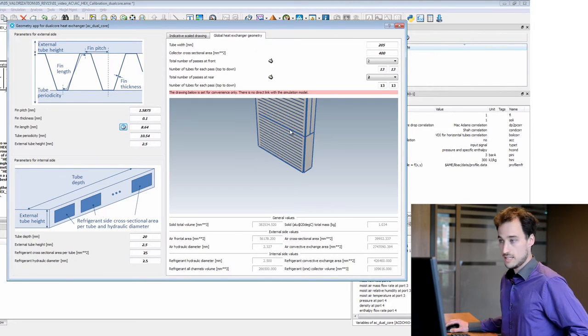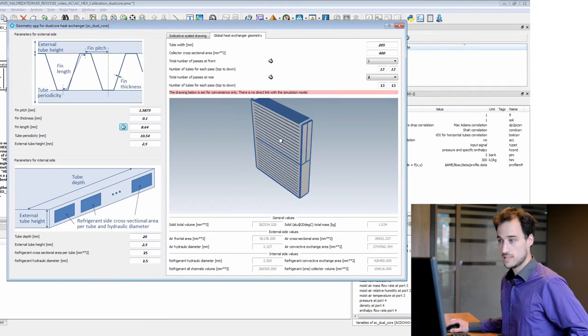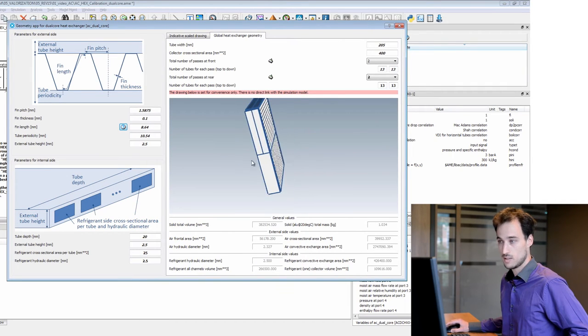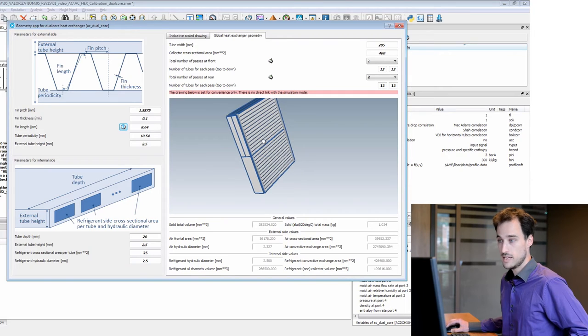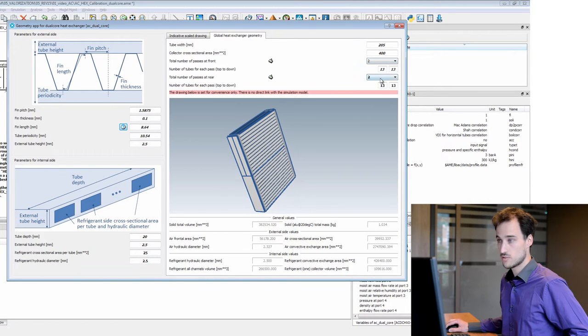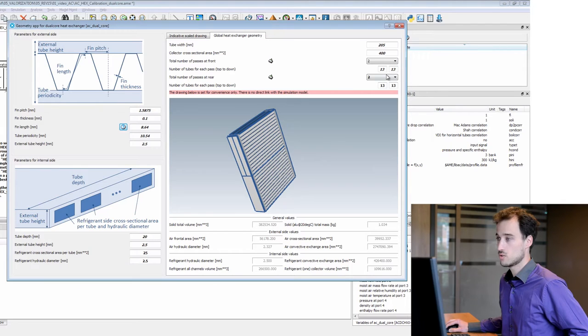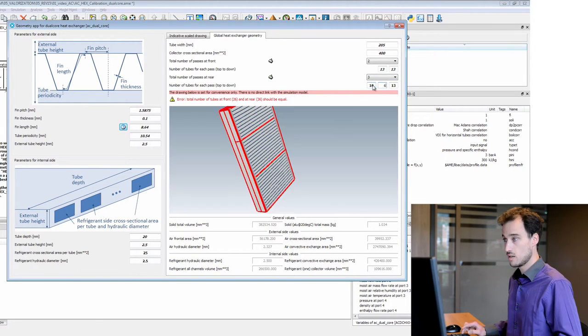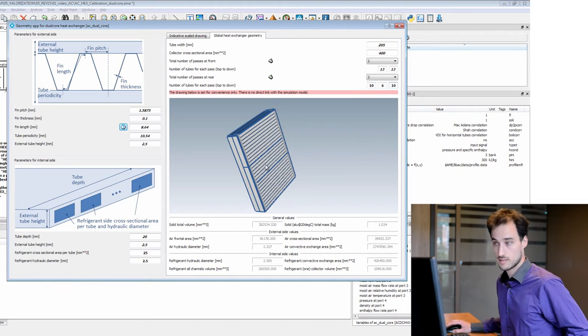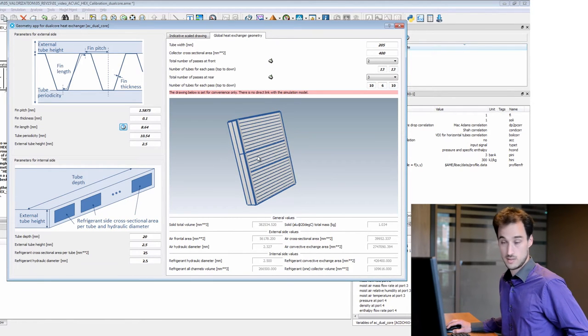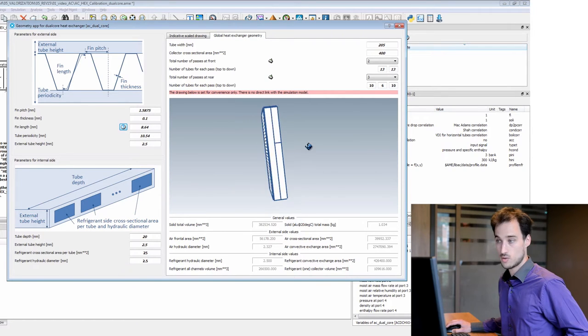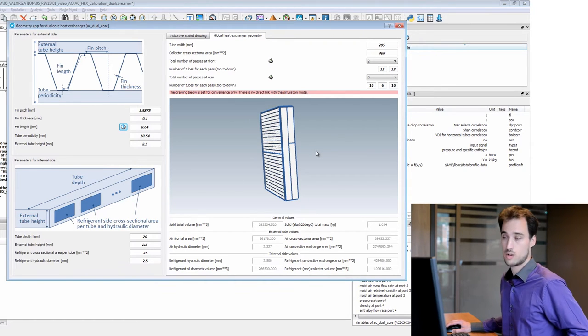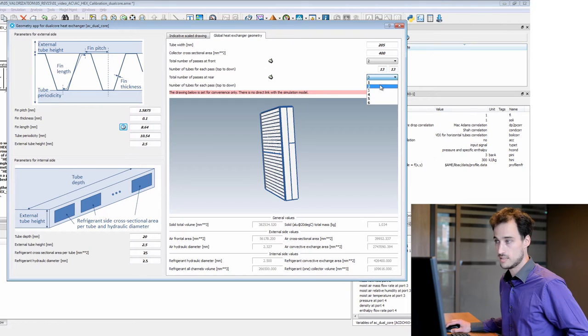A second panel here shows you the heat exchanger globally with the refrigerant pass. Here this is very flexible, you can change for instance the pass at rear. Consider you have three passes with different tubes for each pass. Here you see you have 10 tubes, 10 tubes, 6 tubes, 10 tubes again. So you can set whatever architecture of your dual core you want, and very easily.